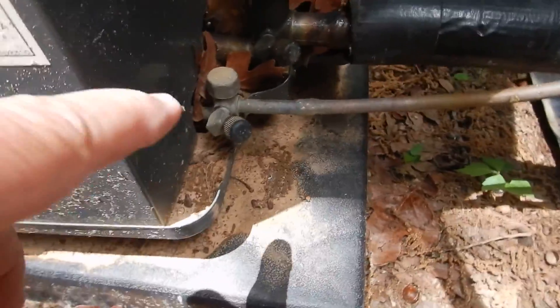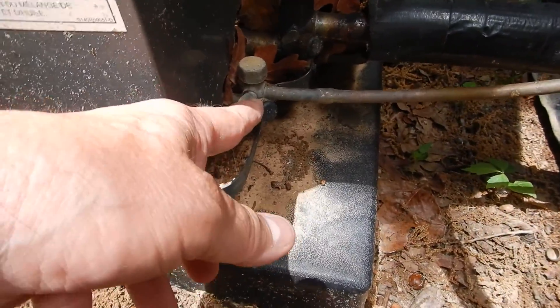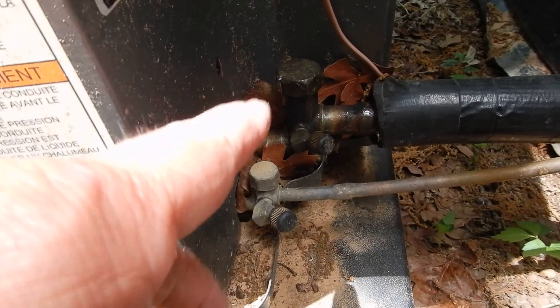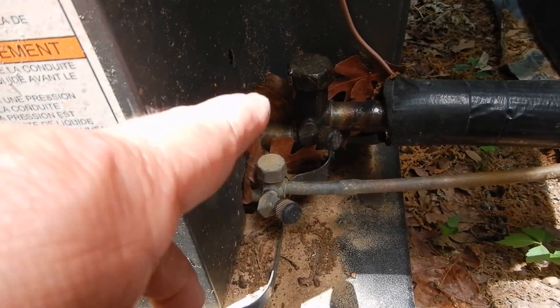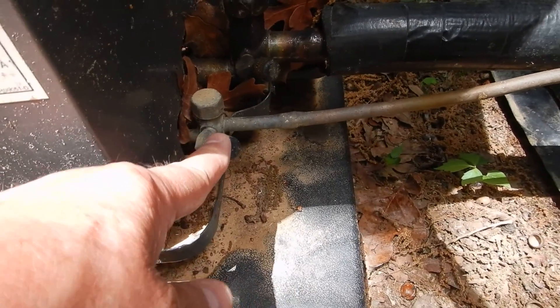These are Schrader valves — look that up in the dictionary, Schrader valve caps. These are your refrigerant piping service valve outlet caps, and they should be anti-theft. They're not — wrong kind of caps.